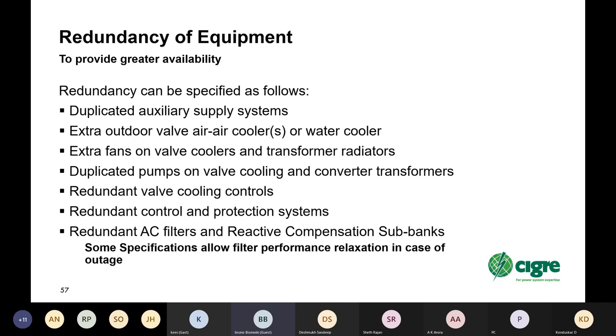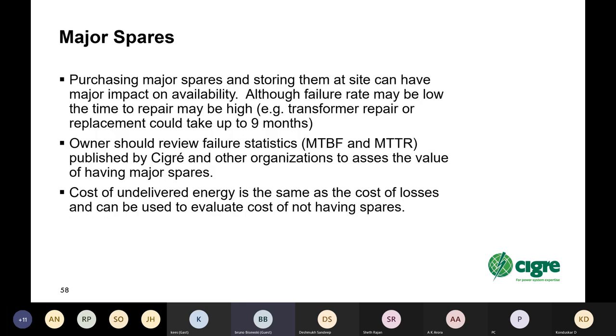Redundancy of equipment, we've already looked at this to some extent, so I'm just going to skip over it. Redundancy of equipment does give you some better reliability or better capability, especially in case of partial outages. For instance, redundant controls, redundant protection systems, redundant filters, reactive compensation allow you to operate to full capacity even when there's some equipment that is out. Major spares can have a major impact on reliability. For transformers, repair or replacement could take 9 to 12 months, and that can really reduce the availability and really put you at a disadvantage financially if your facility or a pole of that facility is out of operation for that long.